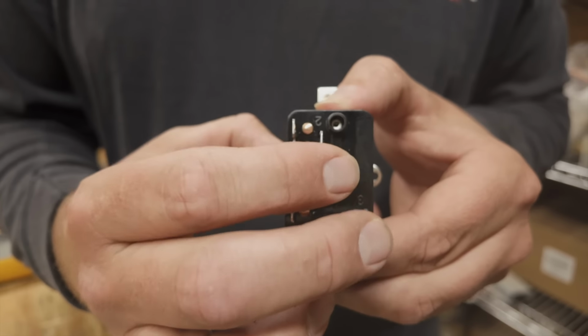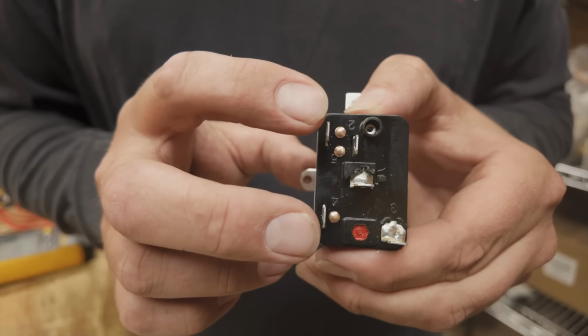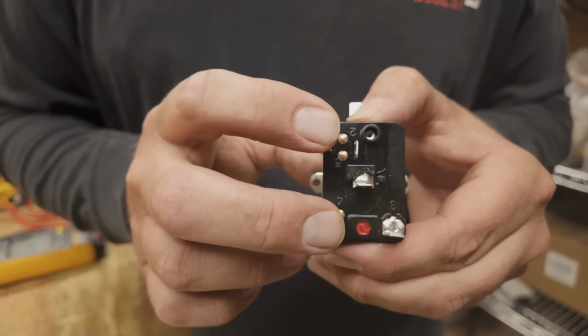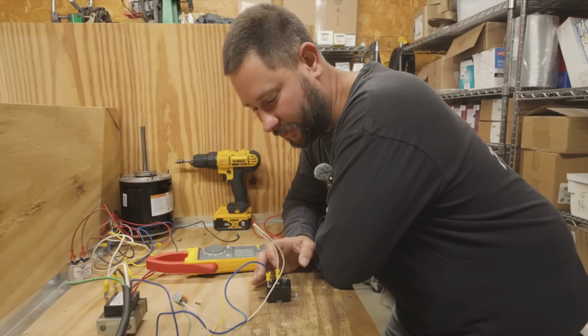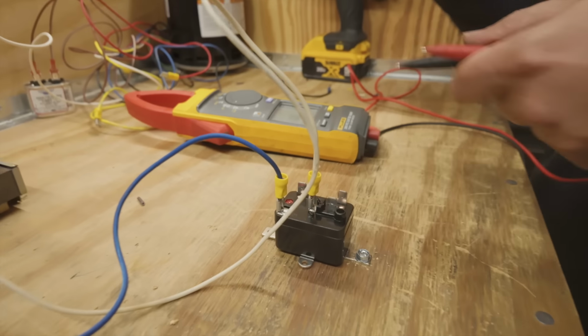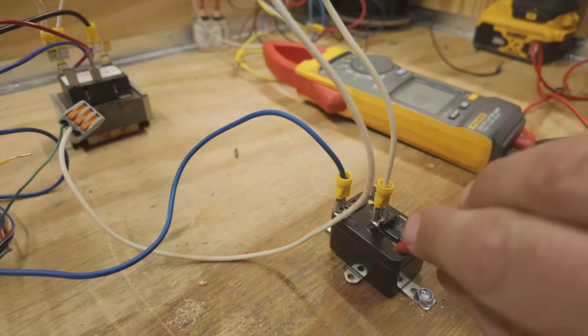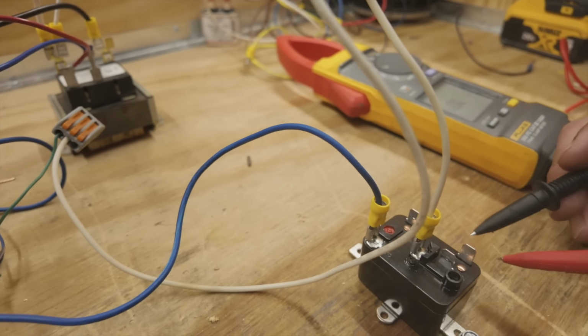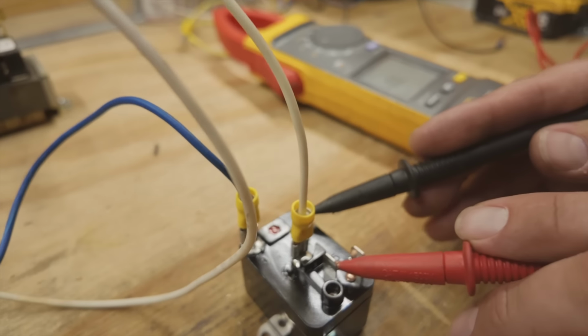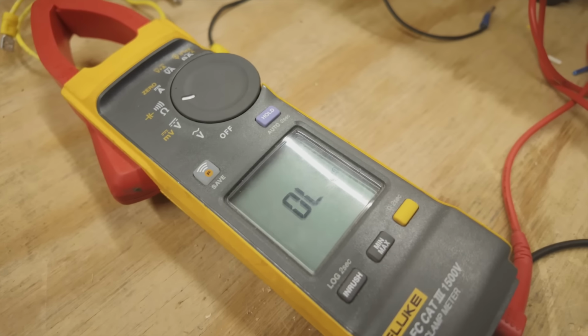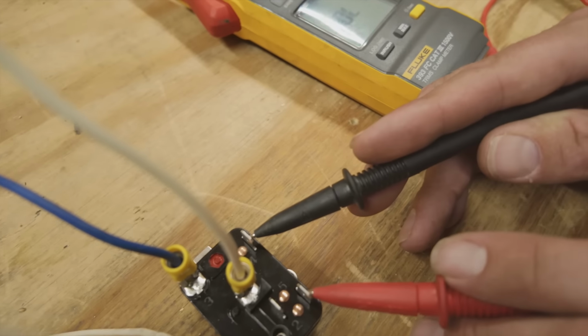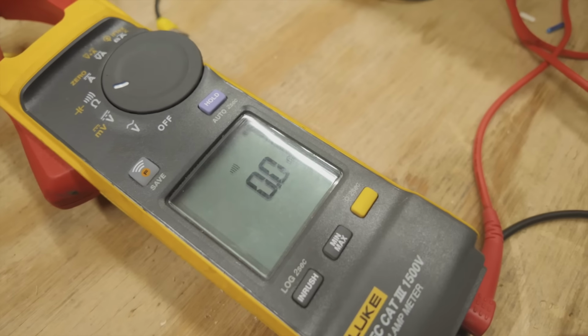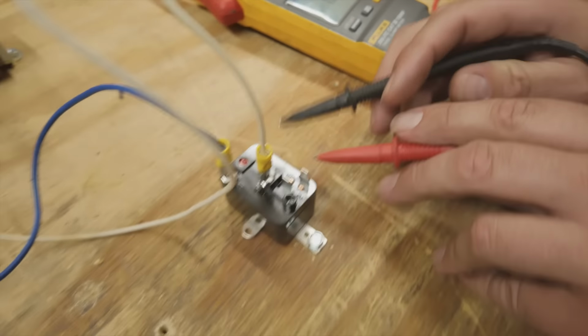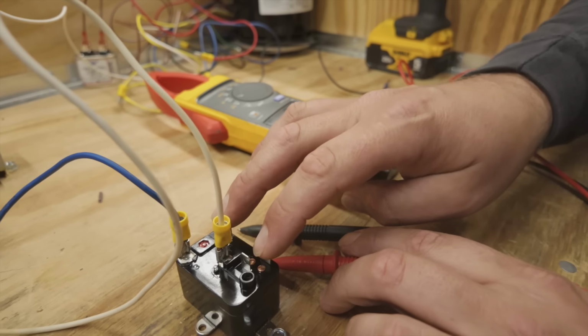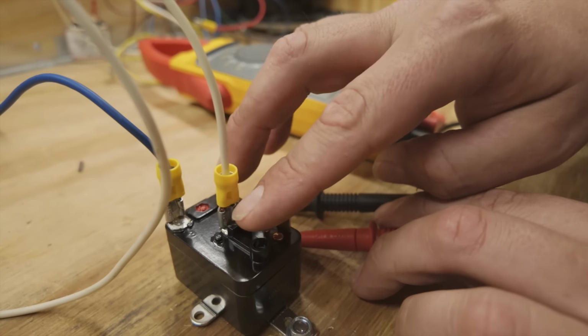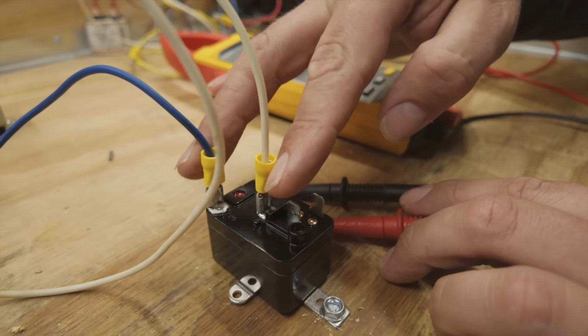So whenever we get voltage here, 4 and 5 will open and 2 and 4 will close. I've got the coil wires connected between 1 and 3. And right now, of course, we don't have a call. So we don't have any voltage here. Between 2 and 4, we don't read anything. This is a normally open set of contacts. Between 4 and 5, we read continuity because it's closed. It's a normally closed set of contacts. But this 4 and 5 should open and 4 and 2 should close whenever we do receive 24 volts.